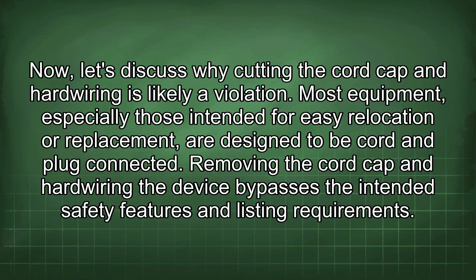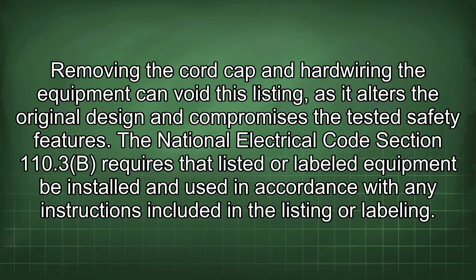Equipment is often listed by a testing laboratory, such as Underwriters Laboratories, Intertek, or Canadian Standards Association. This listing signifies that the equipment has been tested and meets specific safety standards. Removing the cord cap and hardwiring the equipment can void this listing, as it alters the original design and compromises the tested safety features. The National Electrical Code Section 110.3(B) requires that listed or labeled equipment be installed and used in accordance with any instructions included in the listing or labeling. Cutting off the cord cap violates this requirement.